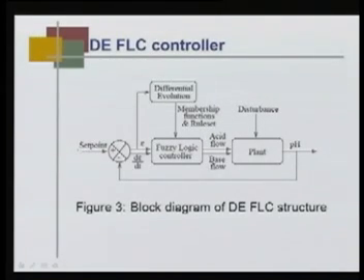Normally the pH set point is 7, and here the error and the derivative of the error are the 2 input variables to my fuzzy logic controller, and I utilize differential evolution to optimize the parameters of the fuzzy logic controller. The output of the fuzzy logic controller is either acid flow rate or base flow rate to the plant.